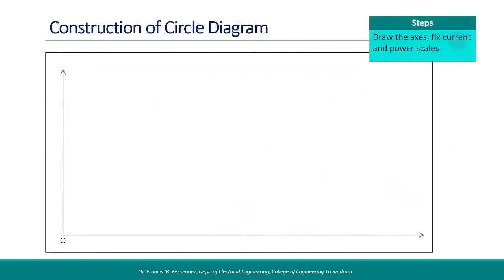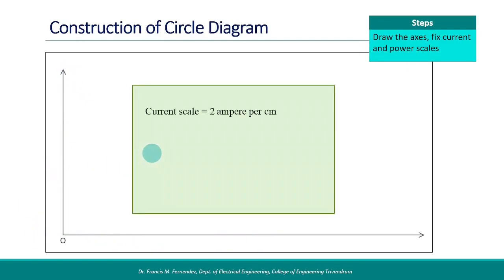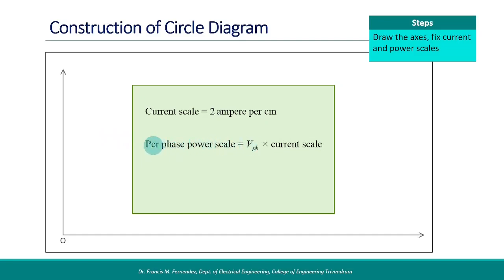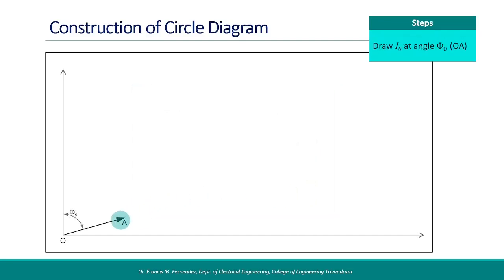The first step in constructing the circle diagram is to draw the horizontal and vertical axes and fix the current and power scales. For example, we may take 2A per centimeter for current, which may vary depending on the current rating of the machine. The power scale is related to the current scale: per-phase power scale equals phase voltage multiplied by the selected current scale. If the rated phase voltage is 240 volts, then the power scale is 240 × 2 = 480 watts per centimeter. Start by marking the no-load phase current I0, counting the current scale at an angle phi0 from the vertical axis, which represents voltage.